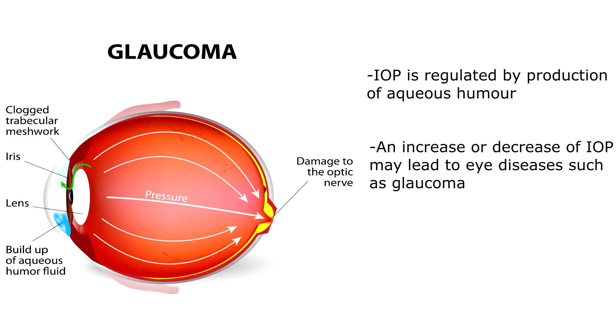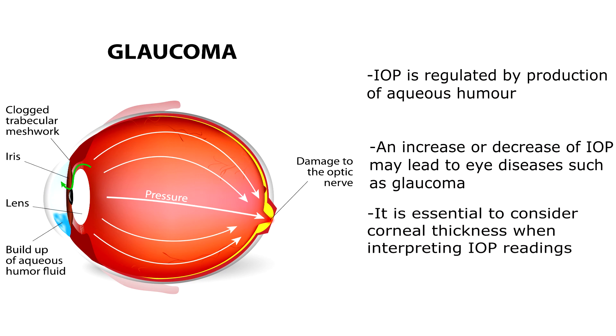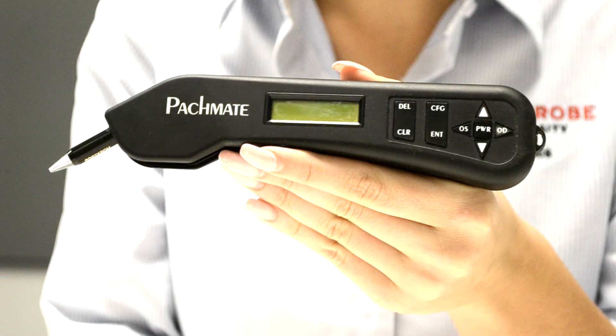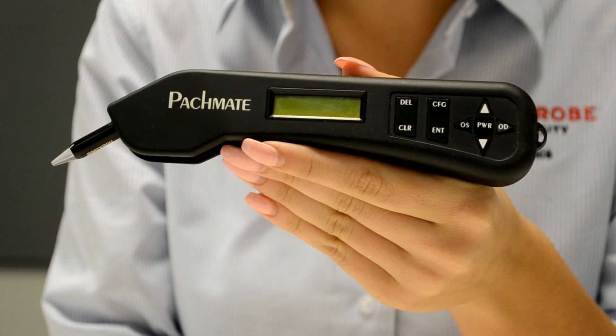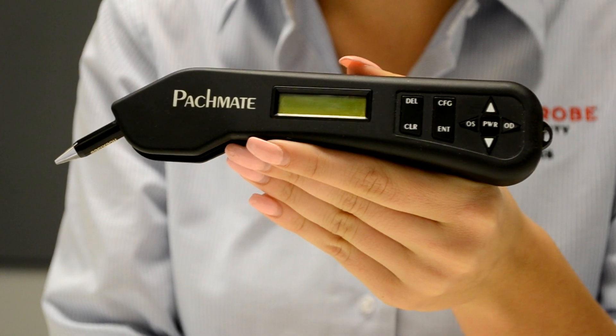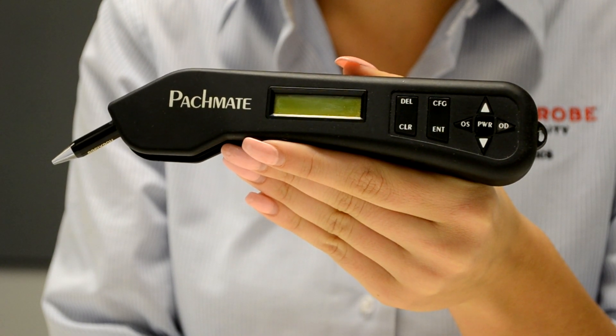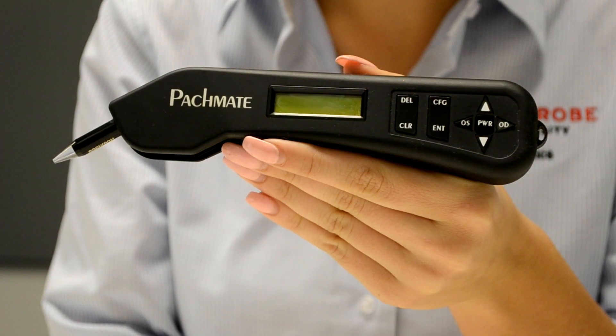IOP readings are linked to corneal thickness and thus interpretation of IOP readings may vary. Therefore it is important to measure a patient's corneal thickness, which can be done through an instrument called a pachymeter. Pachymetry readings can be taken before or after IOP readings as research has shown there is no variation in measurements. There are many brands and types of pachymeters, however for the purposes of this video we will be using and discussing the settings of the pachymeter brand PACHMATE DGH55.